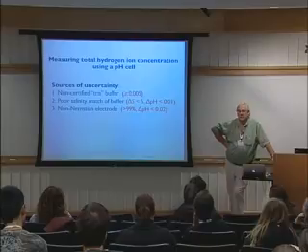If those are good buffers, you can do it. That's often the only way to check an electrode like that. My experience in my lab is that of the electrodes we buy, and we buy the more expensive electrodes, I mentioned the number $200-300, you could buy electrodes a lot cheaper, but buyer beware. With those more expensive ones, probably 1 in 10 is kind of at 99% as opposed to meaningfully better.